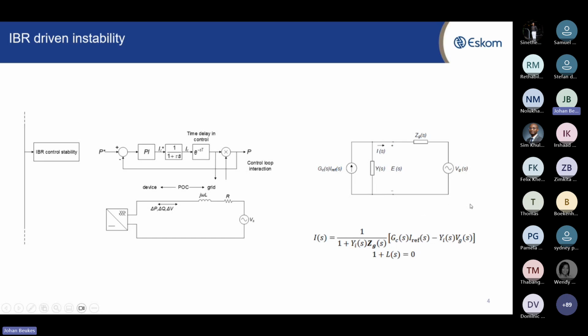in the most simplest way, modeled as a Thevenin equivalent grid with a constant impedance, a grid impedance, and then a Thevenin equivalent current source and a susceptance there. And when you look into the control systems of inverters, then you will see that due to the control of the inverters, you can get a negative impedance. So the inverter creating a negative impedance due to things like control interaction and time delays, and also current controls and PLLs and things like that within the inverter at different frequencies.